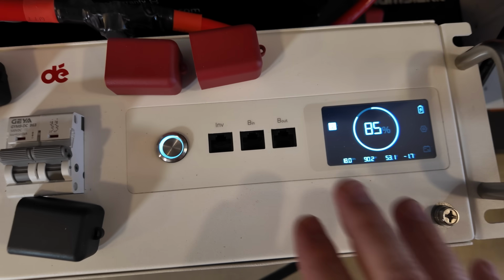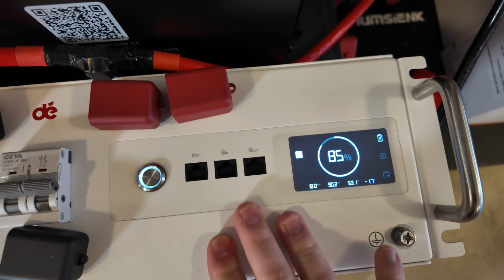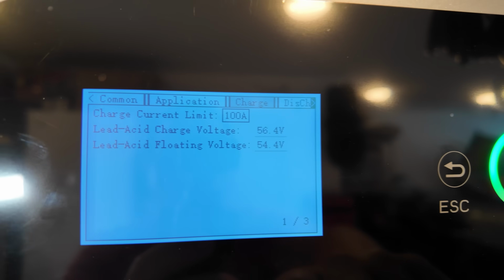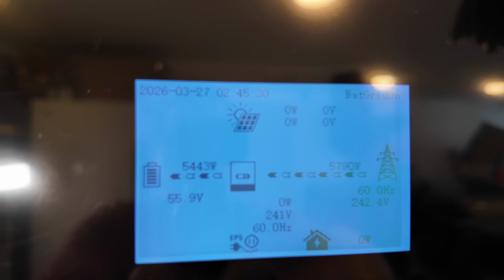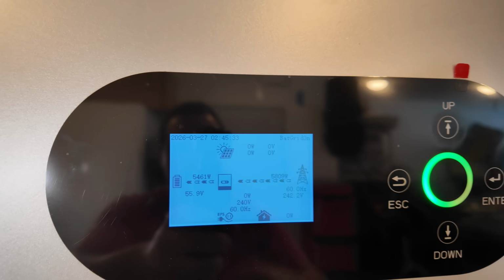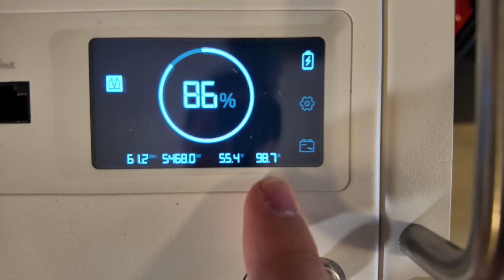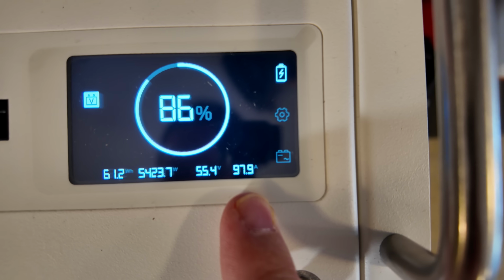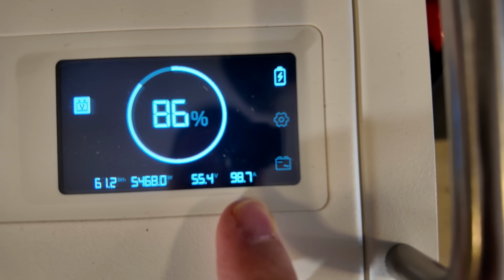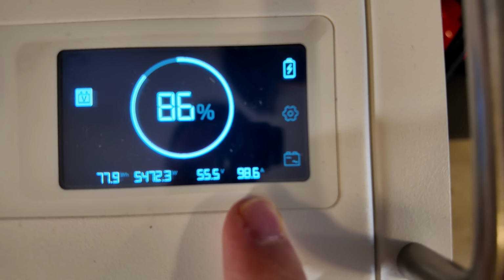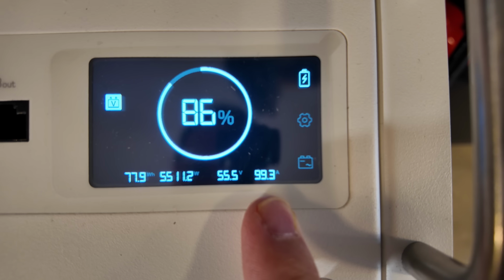Alright, let's test to make sure that this battery can charge at its full charge rate. And I'm going to go for the gusto - we're going to go a full 100 amps. Alright, we're pushing in over 5,000 watts according to the 12,000 XP. Down here on this battery monitoring screen, we can see we're 98, almost 99. There's 97, fluctuating just a little bit. Let's let this run for a few minutes and see if we have any issues.